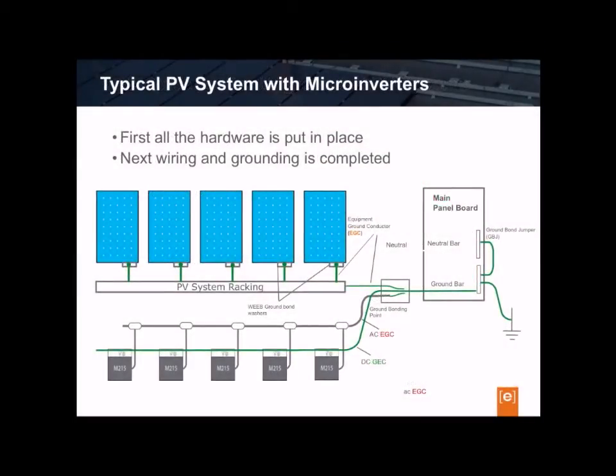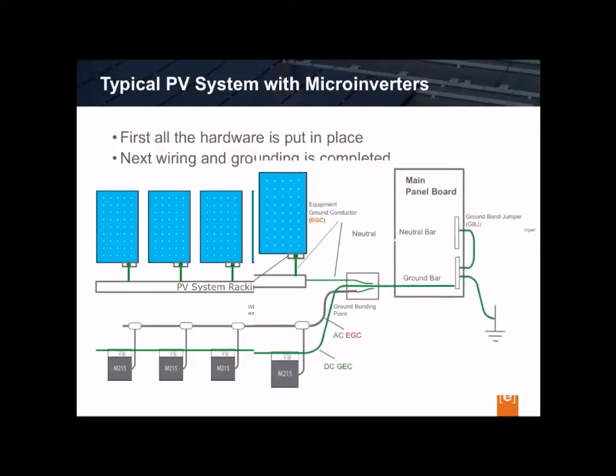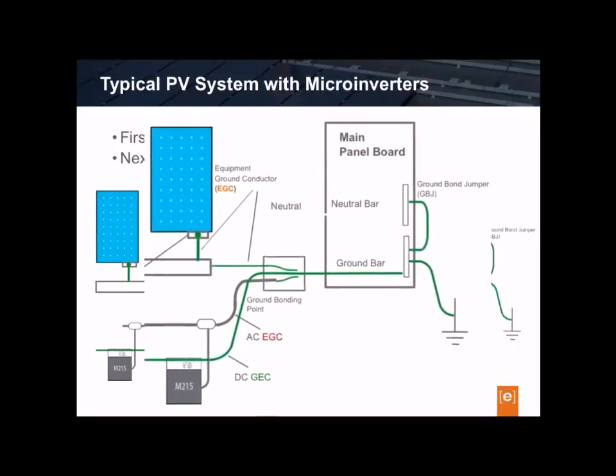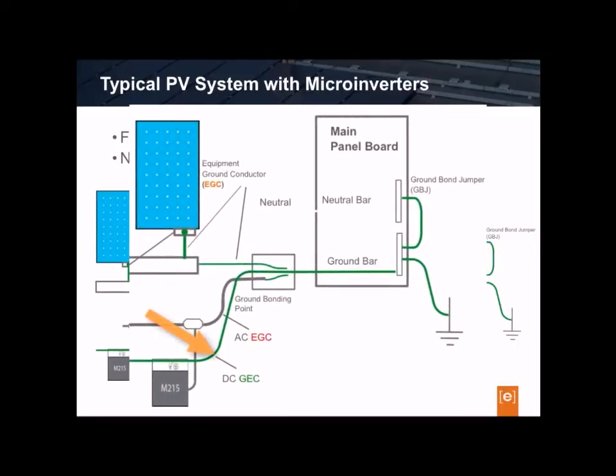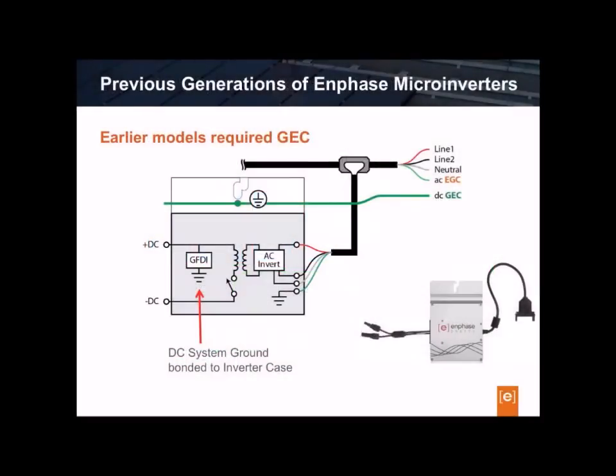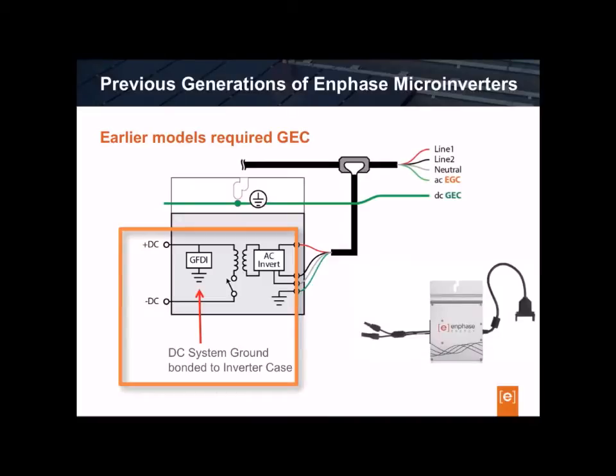Previously, in order to satisfy NEC requirements, microinverter systems were installed with both a GEC to ground the DC power system of the microinverter, and a separate EGC to ground the metal case of the microinverter. For previous generations of Enphase microinverters, a DC-GEC was still required because the input DC circuit was grounded through the ground fault detection and interrupt circuit to the microinverter case, which was the termination point of the DC circuit.